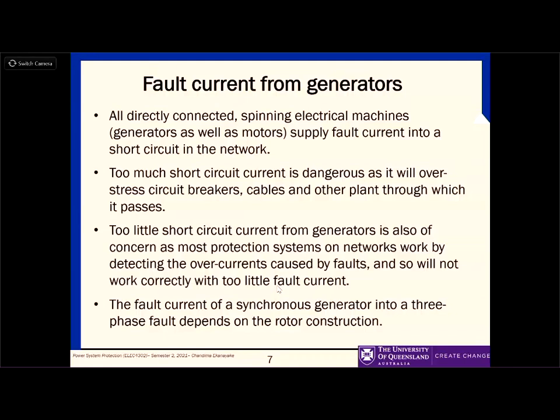The reason is that the fault currents are not balanced, and their magnitudes are very, very large, going through the stator of the generator. The other important thing is that such a large magnitude of current going through the stator produces huge forces on those stator bars. Because can you remember something like F equals B I L somewhere in your studies?